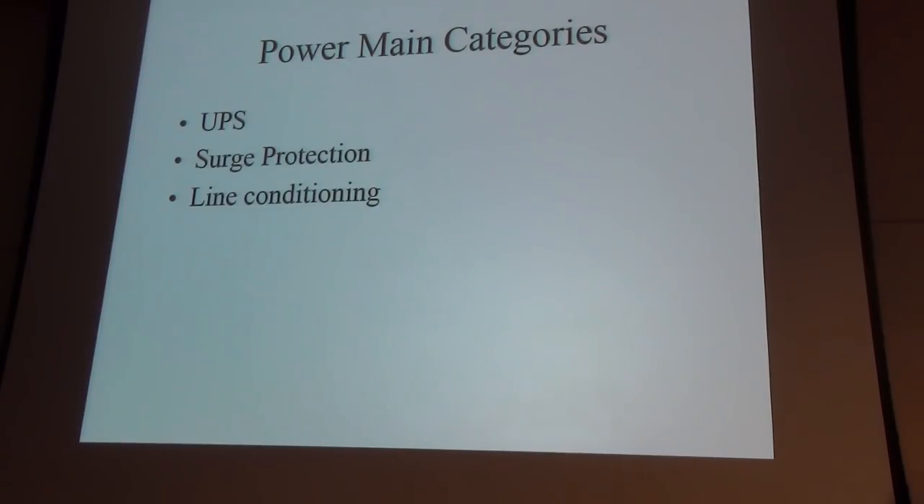Power — we'll use that word quite often. Without power we cannot compute, and we want power all the time. You have uninterruptible power supplies. It's not enough to have a reliable source of power — you also need to make sure it doesn't have surges and spikes, which are bad for your equipment. They condition the power and have surge protection gear. On top of that, we have UPS — banks and banks of lead acid batteries. If there's a sudden outage, you have 5 to 15 minutes of power, alarms go off, and the OS does a graceful shutdown.